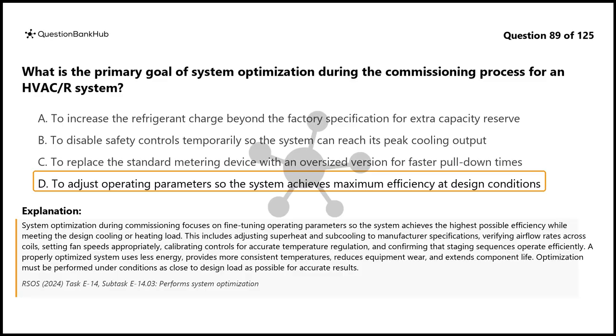This includes adjusting superheat and subcooling to manufacturer specifications, verifying airflow rates across coils, setting fan speeds appropriately, calibrating controls for accurate temperature regulation, and confirming that staging sequences operate efficiently. A properly optimized system uses less energy, provides more consistent temperatures, reduces equipment wear, and extends component life. Optimization must be performed under conditions as close to design load as possible for accurate results.